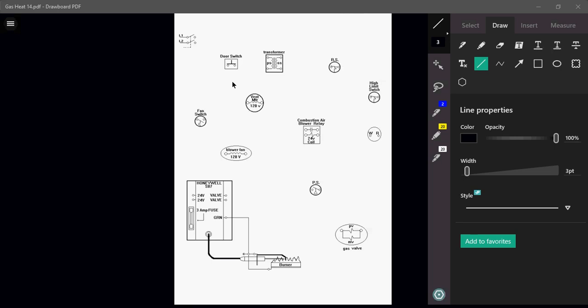Now, when servicing a furnace like this, you can bypass the door switch, maybe simply jump it out or put a magnet on the switch itself just to keep it closed while you're doing your troubleshooting and what have you. But that is the very first part of the operation. Now we have a transformer, which we all know how that works. We have a primary and secondary side. The primary side is obviously going to be supplied with 120 volts. Secondary is going to be 24 volts in most cases.